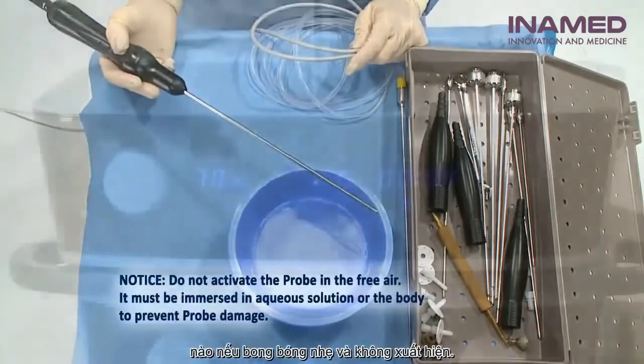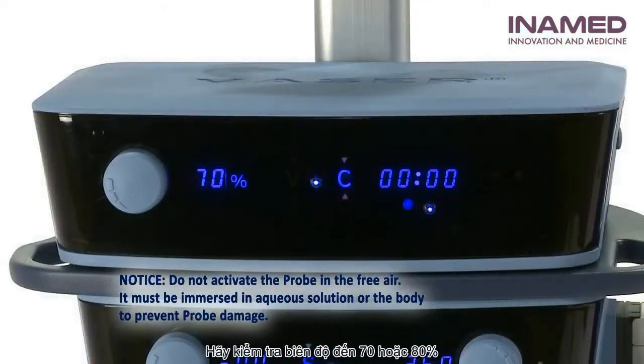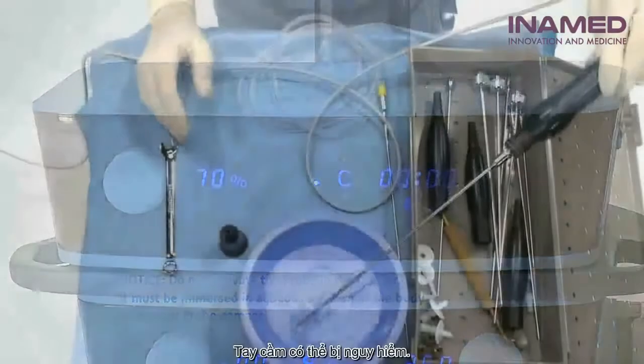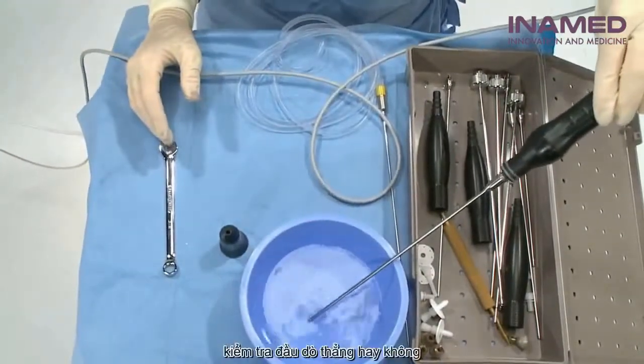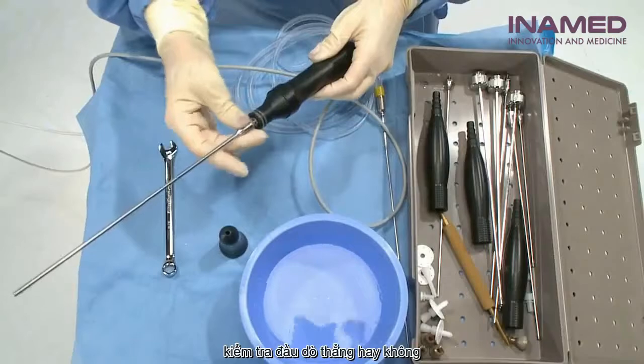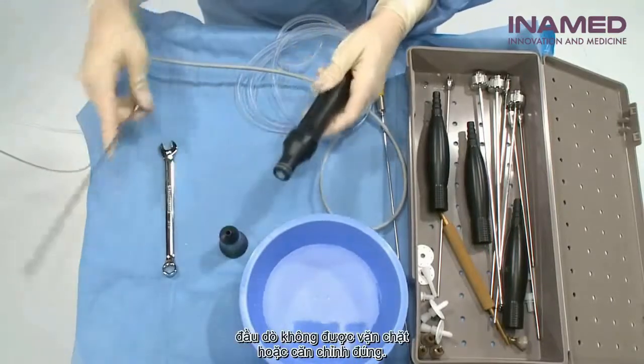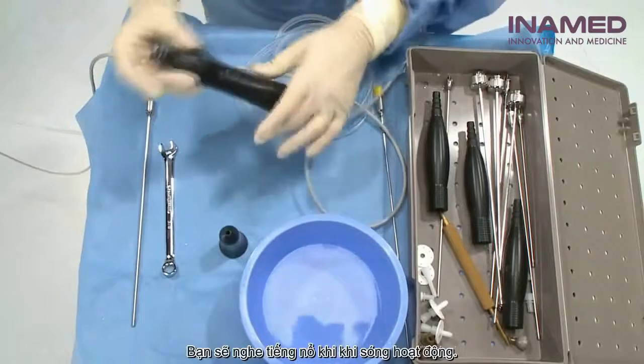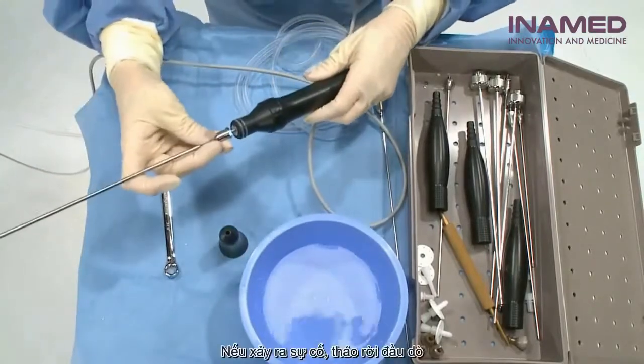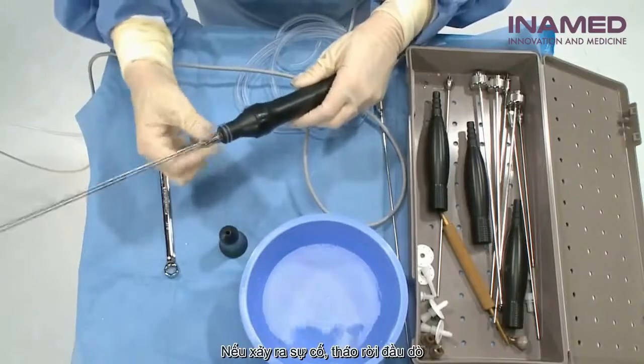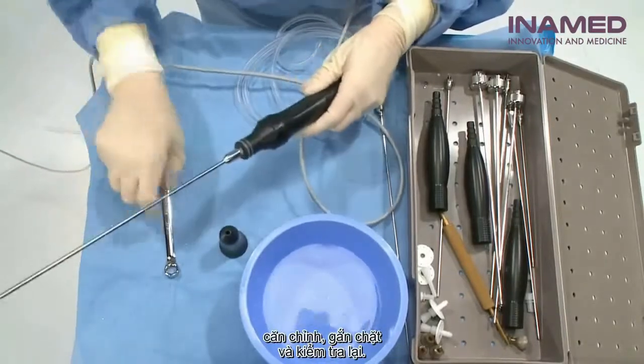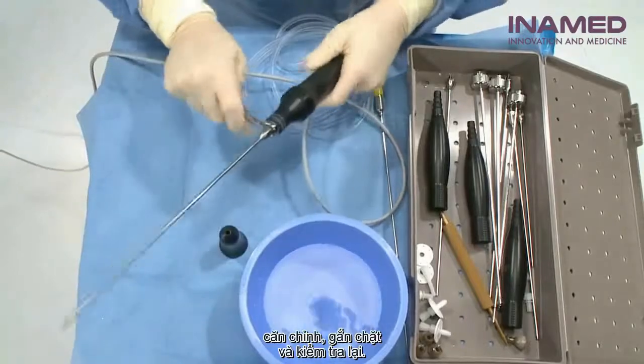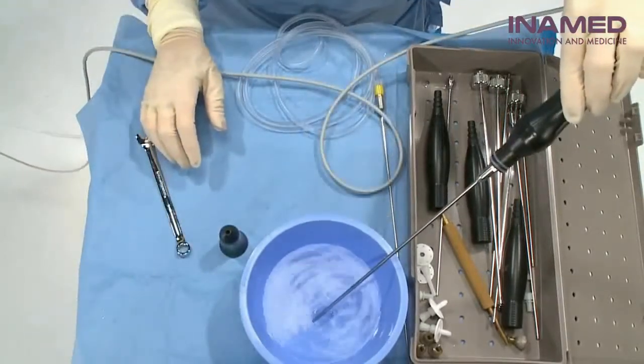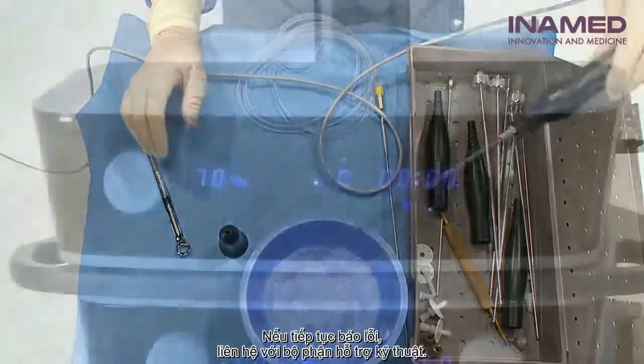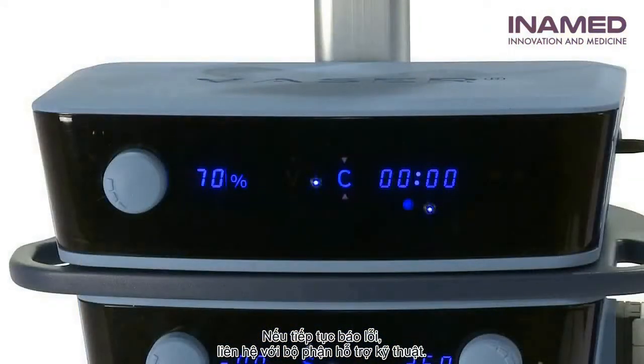If the bubbling is weak or non-existent, check that the amplitude is at 70 to 80%. If the system faults or doesn't do anything, the Vaser handpiece may be damaged. Additionally, check the probe alignment. If the probe is not tightened or aligned correctly, you will usually hear a chattering sound when the ultrasound is activated. If this occurs, disassemble the probe, realign, tighten, and retest. If you continue to experience issues, contact technical support.